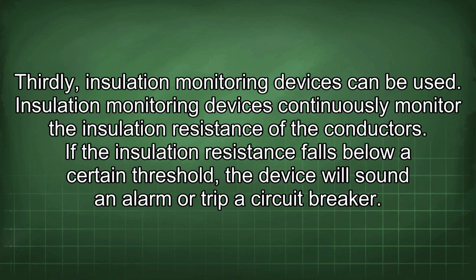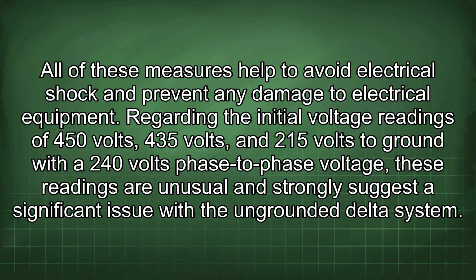Thirdly, insulation monitoring devices can be used. Insulation monitoring devices continuously monitor the insulation resistance of the conductors. If the insulation resistance falls below a certain threshold, the device will sound an alarm or trip a circuit breaker. All of these measures help to avoid electrical shock and prevent any damage to electrical equipment.